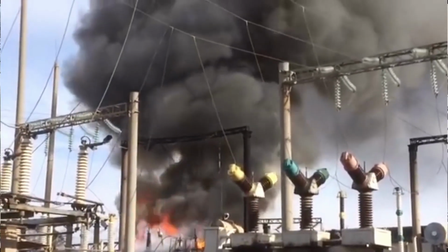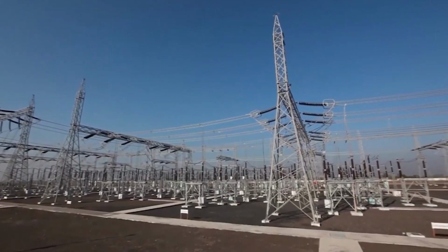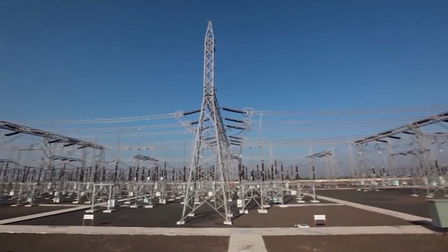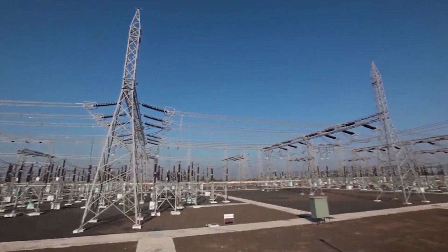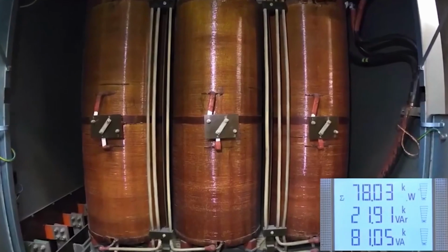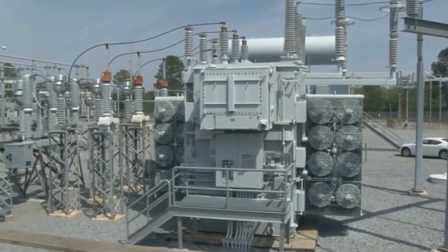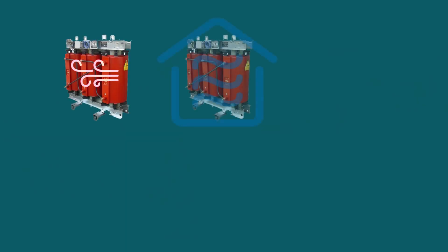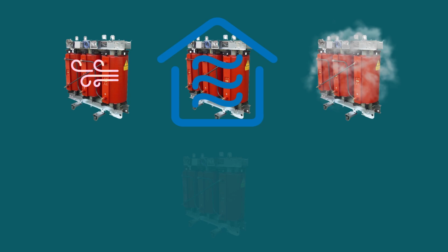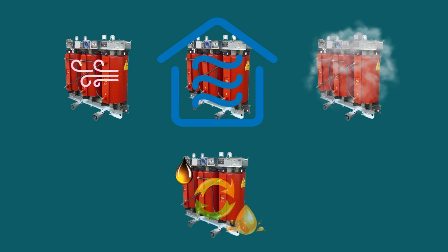In order to prevent the listed consequences, it is necessary to dry the transformer insulation on a periodic basis. Among the most common drying methods, we can distinguish drying with hot air, drying in a vacuum chamber, drying in the vapor phase, circulation of hot dehydrated oil with oil spraying and vacuuming. However, these methods have disadvantages that disallow the drying process to be as efficient as possible.